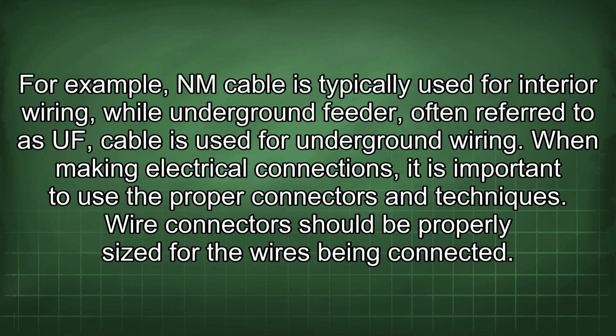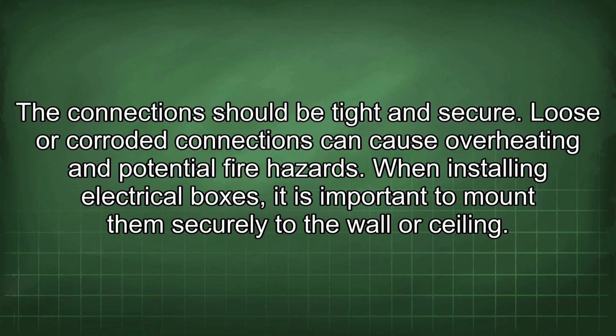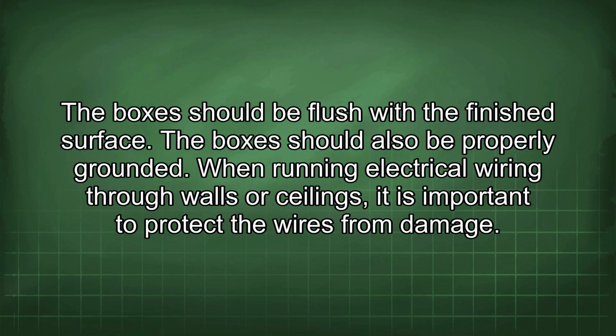When making electrical connections, it is important to use the proper connectors and techniques. Wire connectors should be properly sized for the wires being connected. The connection should be tight and secure. Loose or corroded connections can cause overheating and potential fire hazards. When installing electrical boxes, it is important to mount them securely to the wall or ceiling. The boxes should be flush with the finished surface. The boxes should also be properly grounded.